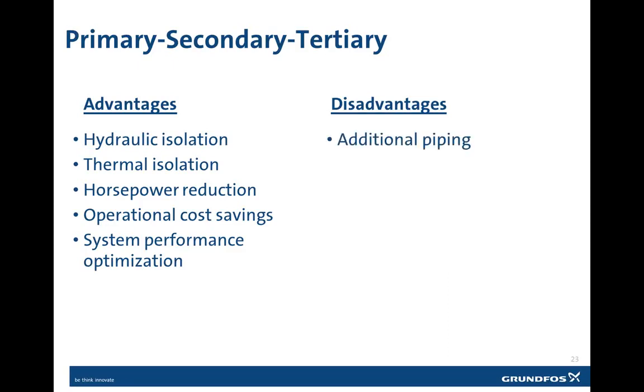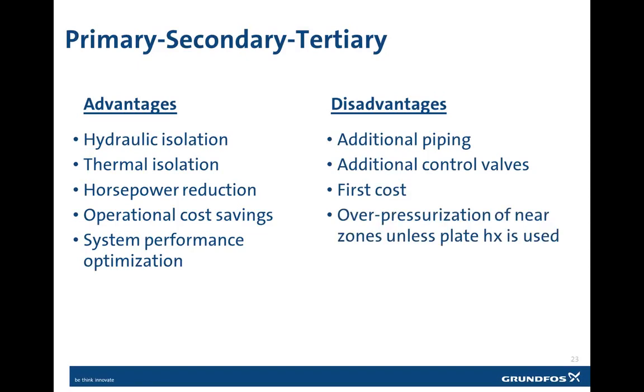Some of the disadvantages: there will be additional piping costs. There will be additional control valves needed for the application. There's going to be an additional first cost for the additional pumps, heat exchangers, and design. And there could also be an over-pressurization of some of the near zones if you're not using a plate heat exchanger, which with this type of system would result in more pumps being needed for the system.